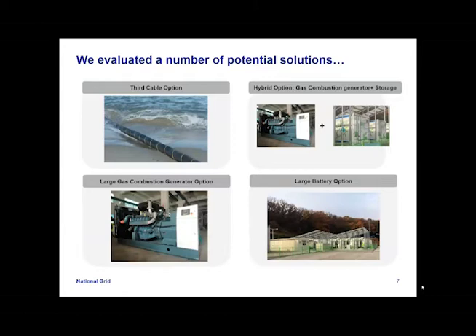We also looked at doing just a very large battery, but we actually took a hybrid option. The reason is that we still needed to charge the battery, and a battery alone, given the duration we need to maintain the peak, wasn't really a good option based on current energy storage technology. So we installed a small emergency generator, roughly 10 megawatts, as well as a large energy storage facility: a 48 megawatt-hour battery, 6 megawatts, 8-hour duration.